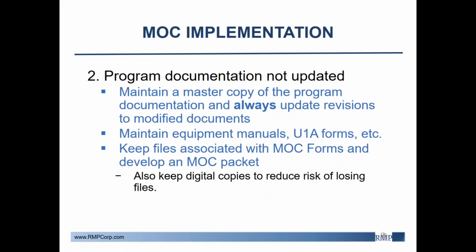Second, the program documentation is often not updated. The solution to fix this is first to maintain a master copy of the program documentation and always update revisions to modified documents, to maintain equipment manuals, U1A forms, etc., to keep files associated with MOC forms, and develop an MOC packet. Also, keeping digital copies to reduce the risk of losing files is recommended.